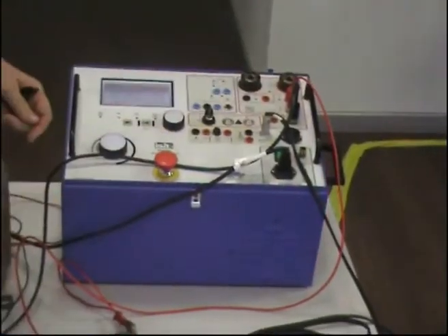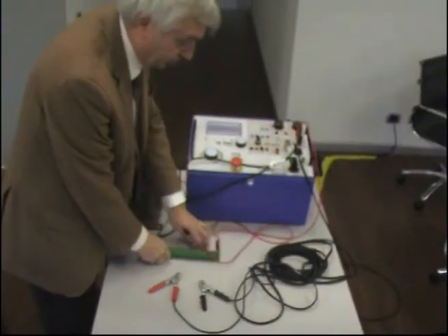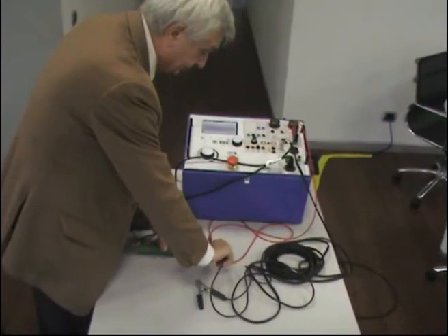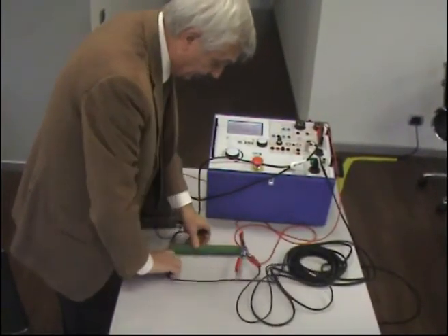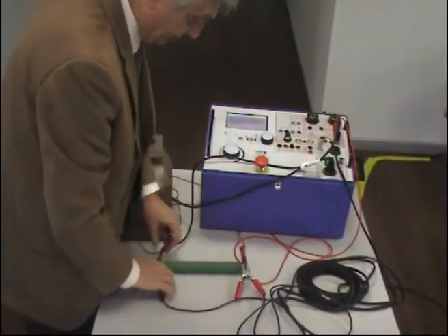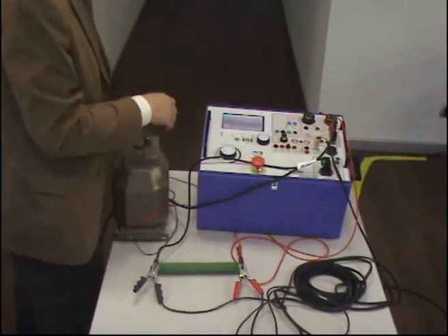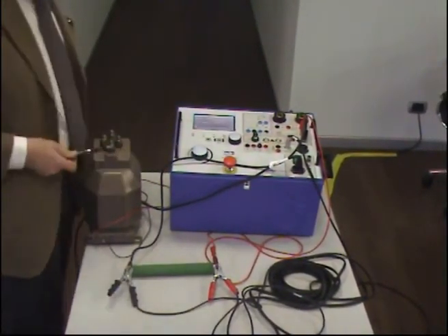this way. Next, again, as before, I have to measure the voltage drop across my resistor, and this is what I do. With the same cable, I can measure the voltage drop, and again, the test set will measure the resistance and compute the voltamp rating.